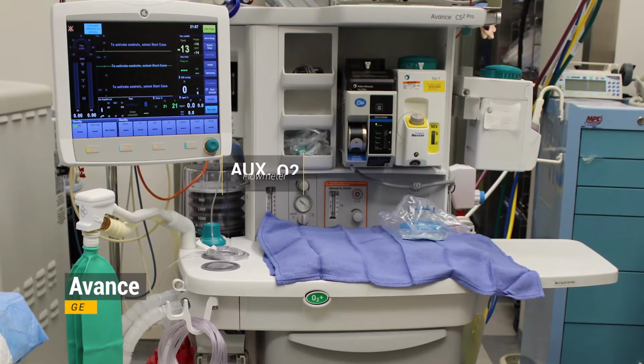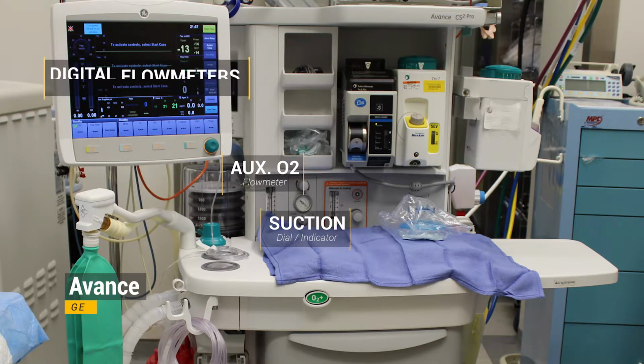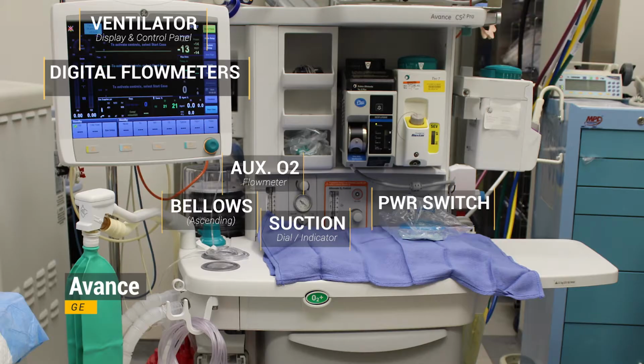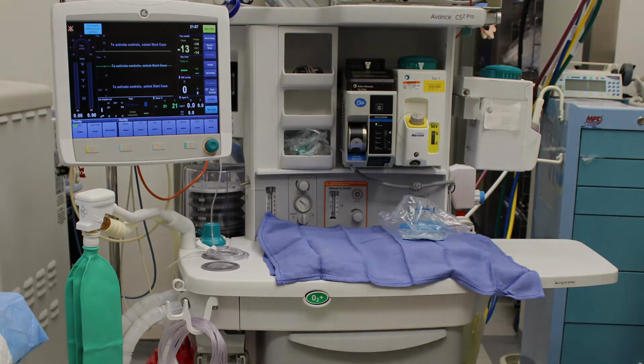The Avance is similar to the Aestiva in many ways. The key differences are digital flow meters with on-screen controls instead of mechanical dials, and an automated self-checkout procedure. A manual leak check can be performed on this machine in the same manner as described previously.